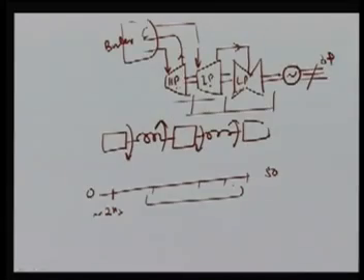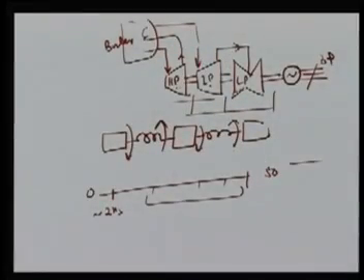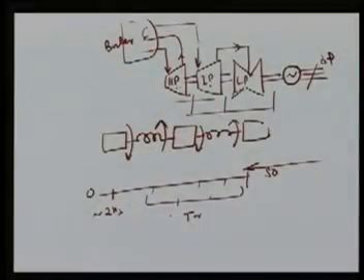Normally one term is very popular, synchronous resonance, because if your system has a compensated transmission line, there is a possibility that some frequency of the current entering the system may coincide with these frequencies of oscillations, and then there will be huge resonance. If that frequency matches the torsional modes of frequencies, a huge torque is developed inside the shaft and the shaft may be broken. That is called subsynchronous resonance, because at that frequency the resonance has occurred. So, this is your torsional mode, and the 2 hertz, as I said, is a local oscillation mode.